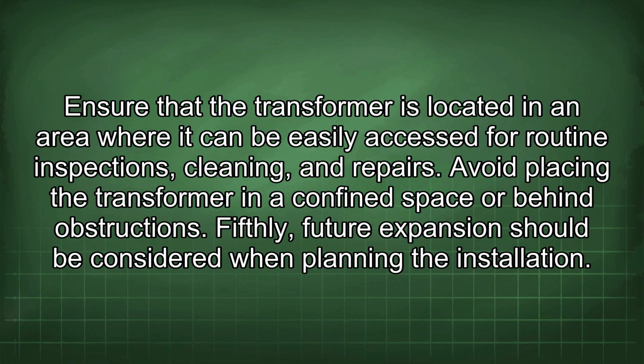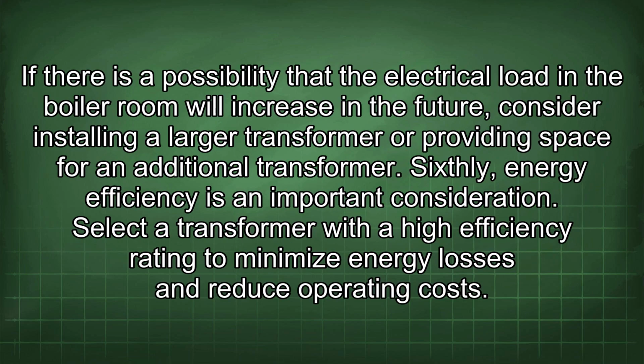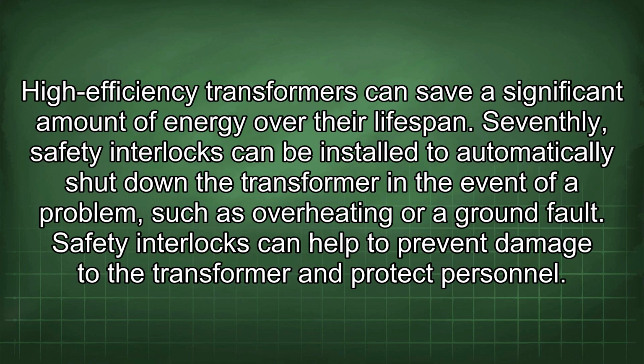Fifthly, future expansion should be considered when planning the installation. If there is a possibility that the electrical load in the boiler room will increase in the future, consider installing a larger transformer or providing space for an additional transformer. Sixthly, energy efficiency is an important consideration. Select a transformer with a high efficiency rating to minimize energy losses and reduce operating costs. High efficiency transformers can save a significant amount of energy over their lifespan.